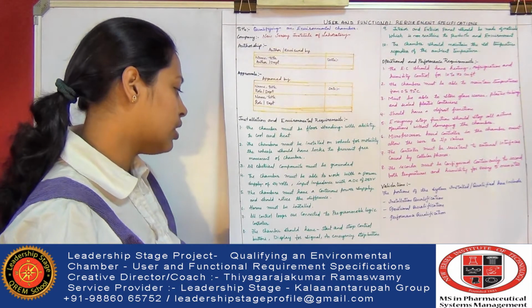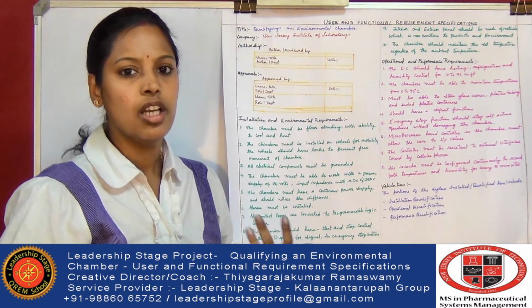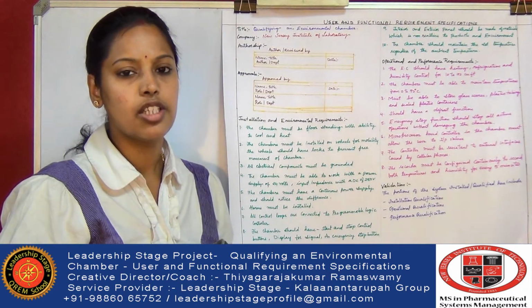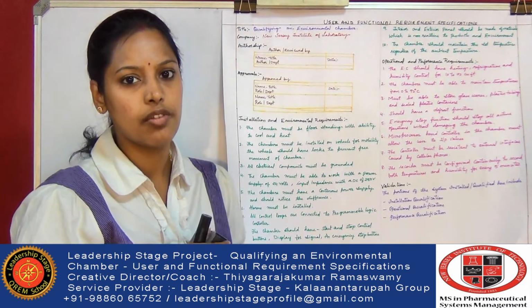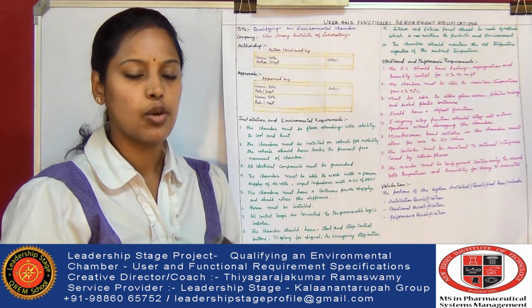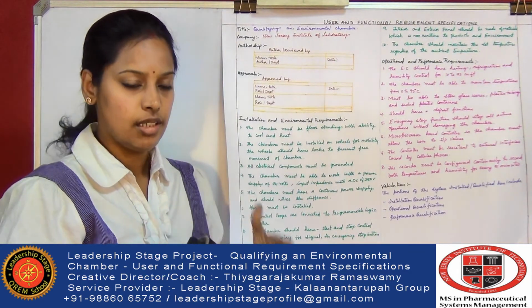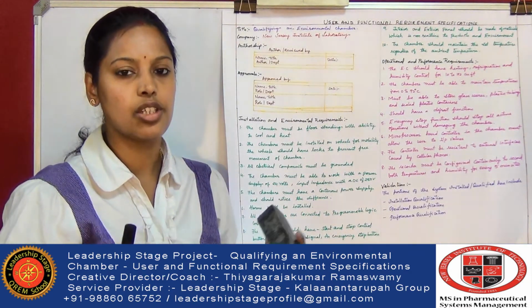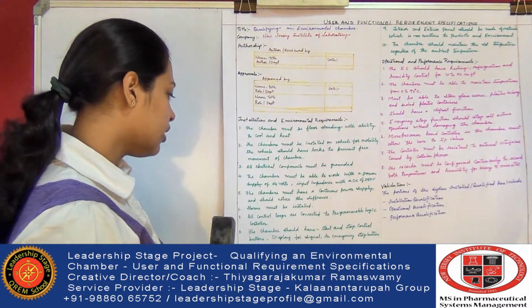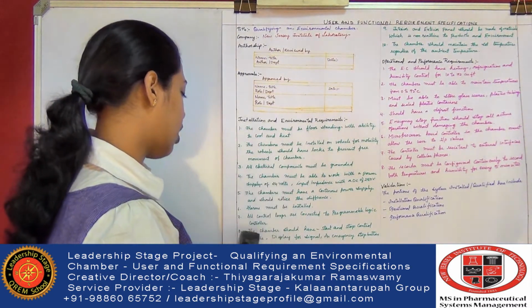And during an emergency, the chamber should have alarms in such a way that they do not disturb the internal processing of the system. Like when you have a mixer going on inside the environmental chamber, it should not disturb the mixer content, but instead it should give the alarm. So that is one of the environmental requirements.